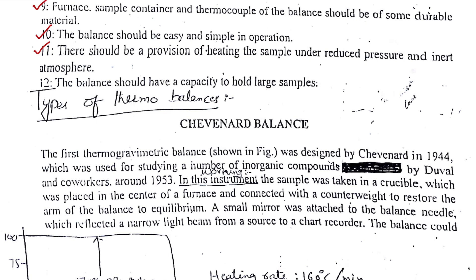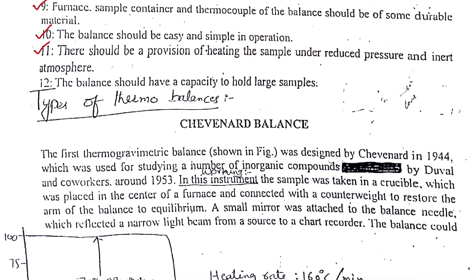There should be a provision for heating the sample under reduced pressure and inert atmosphere. If we close the sample in a closed chamber and reduce the pressure to create an inert environment, this will help achieve good results. The heat provided will only affect the sample, since the presence of air can disturb the sample's nature. A good thermobalance should have provision for an inert atmosphere.